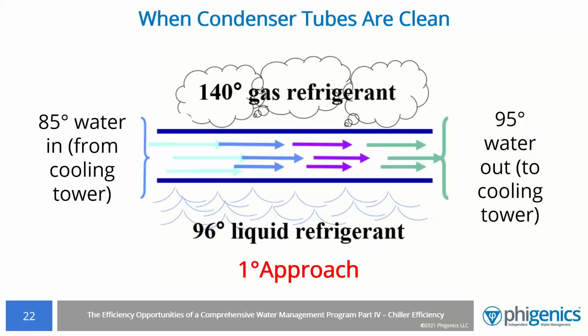Okay, let's take a look at it. It's a single condenser tube. We got water coming from the cooling tower at 85 degrees, going through the tubes, exiting at 95 degrees. So it's a 10-degree load. This is probably full load for this machine. Gas is coming in off the compressor in the range of 130, 140 degrees. It then condenses from a gas to a liquid, gives up its heat to the water through the copper tubes, and that heat is rejected out to the cooling tower.